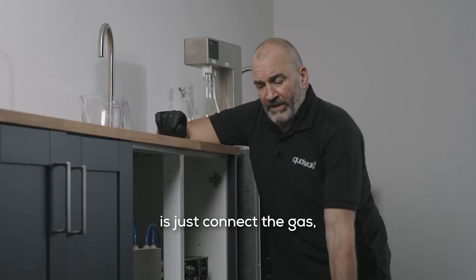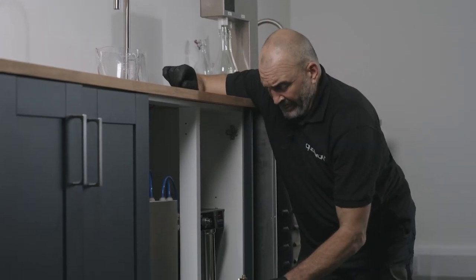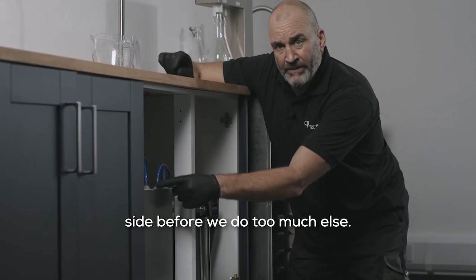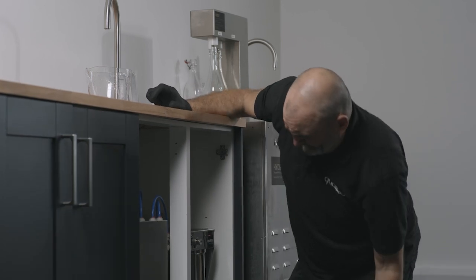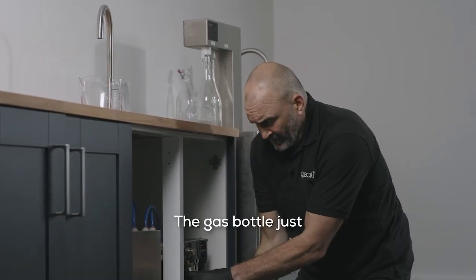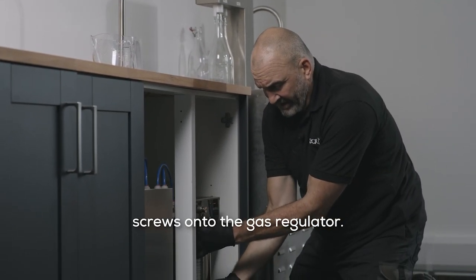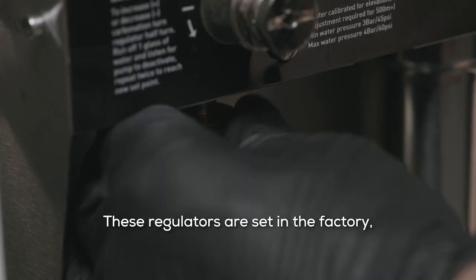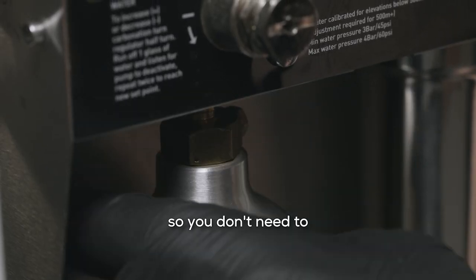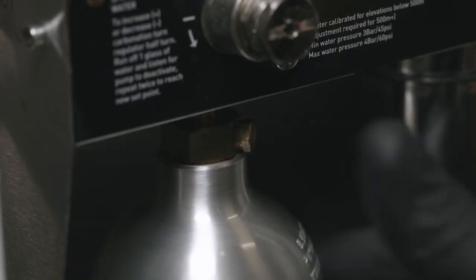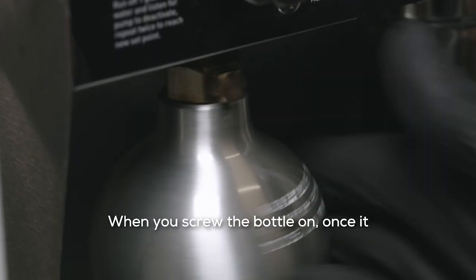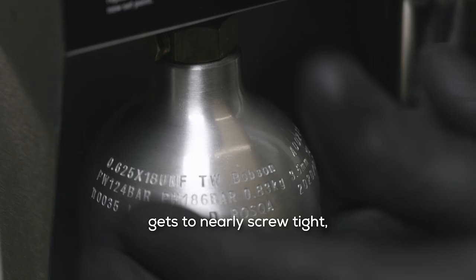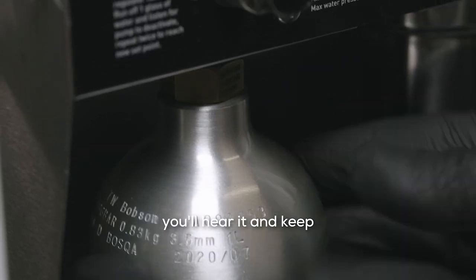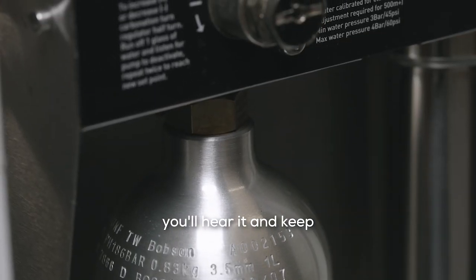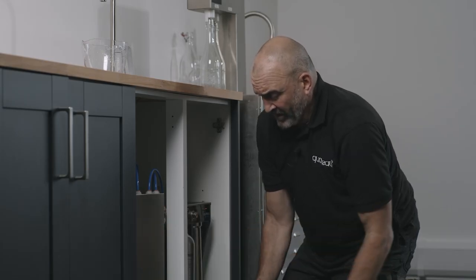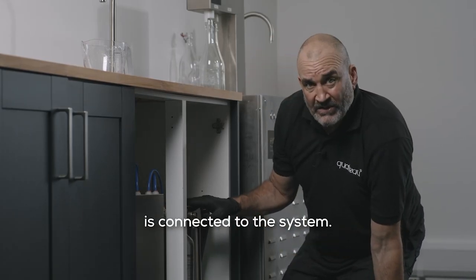What we need to do now is just connect the gas, because we have to commission the chiller side before we do too much else. The gas bottle just screws onto the gas regulator. These regulators are set in the factory, so you don't need to worry about adjusting them. When you screw the bottle on, once it gets to nearly screwed tight, you'll hear a hiss. And keep tightening until the hiss stops. You now know that the gas is connected to the system.